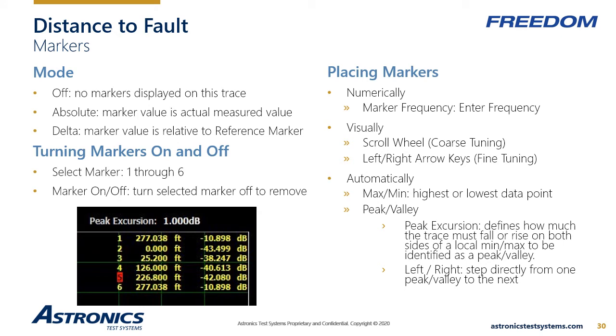Up to 6 markers are available for this single trace. These markers can display absolute measurements or measurements relative to a reference marker. Markers can be placed at user-specified distances or placed visually by scrolling or jumping between peaks and valleys. And again, the user can tell the system what constitutes a peak or a valley by specifying an excursion value.